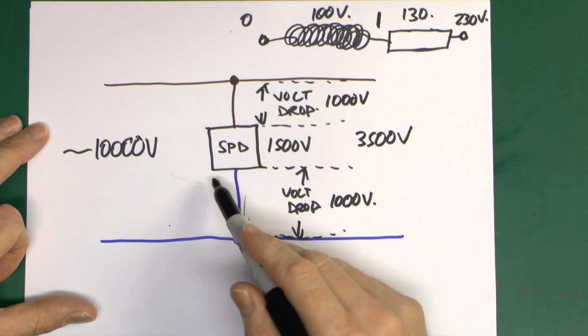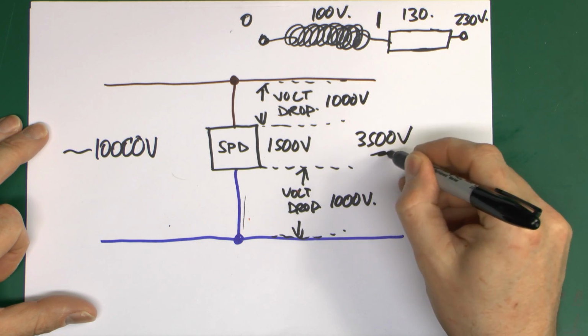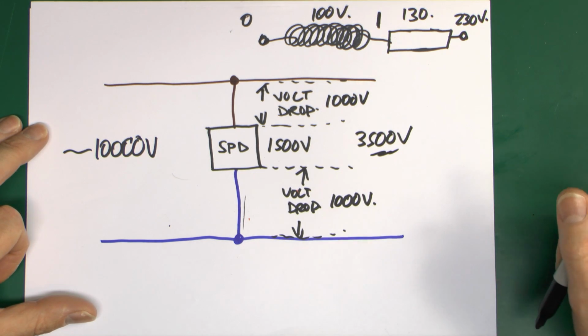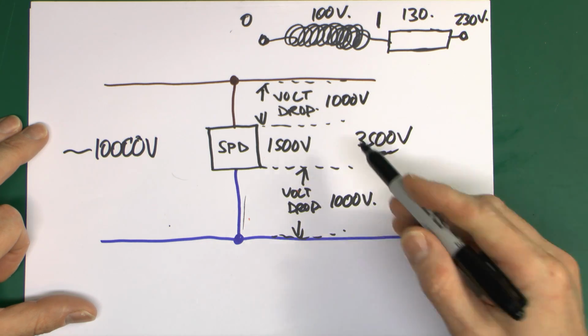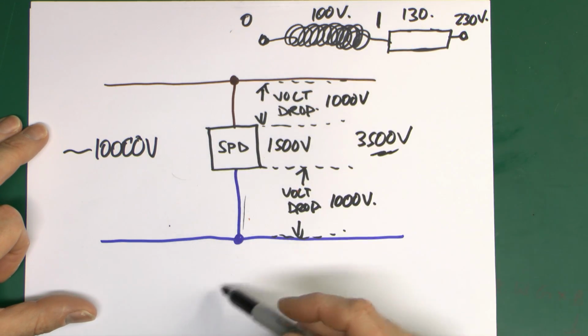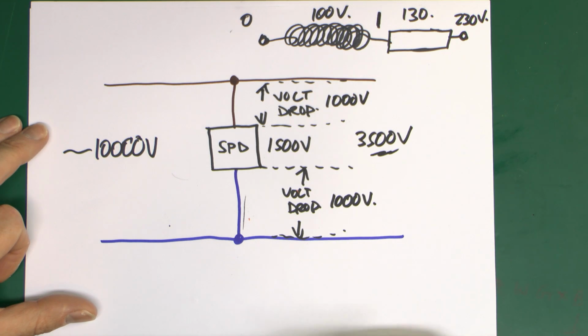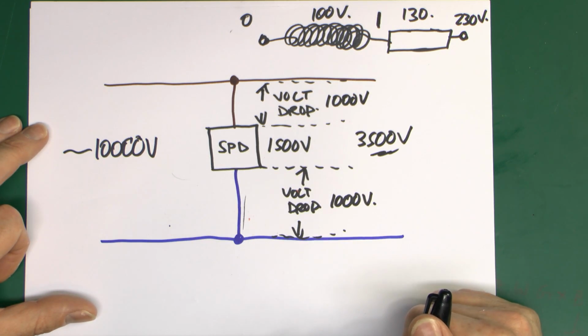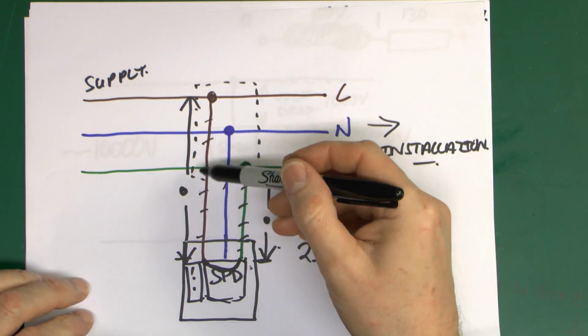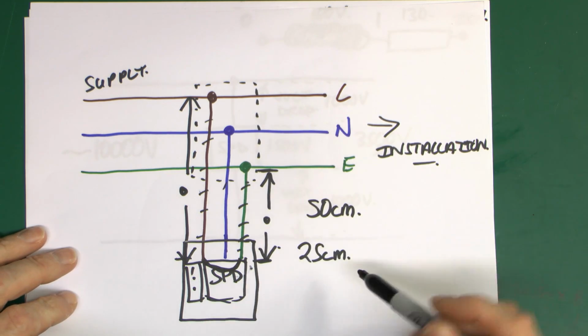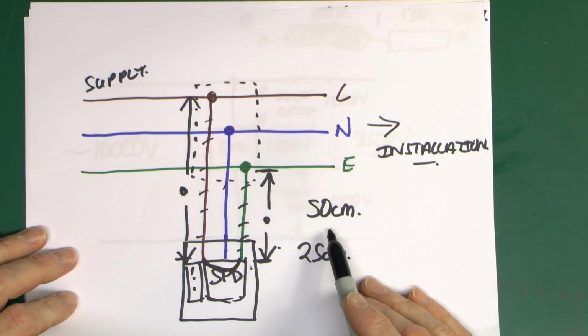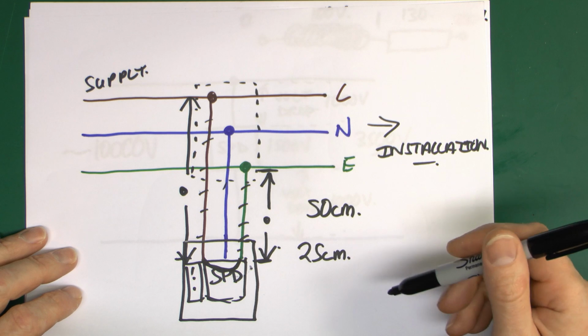And of course that's massively reduced the effect of this thing. That is probably quite enough to still cause damage to equipment connected downstream. And of course, in an extreme case, if these were really long, you might actually end up completely eliminating the point of having this at all. So this is why this length here is absolutely critical, and it's not a case of when you get up to 50 centimeters bad things happen, or when you get to a meter it's no good.